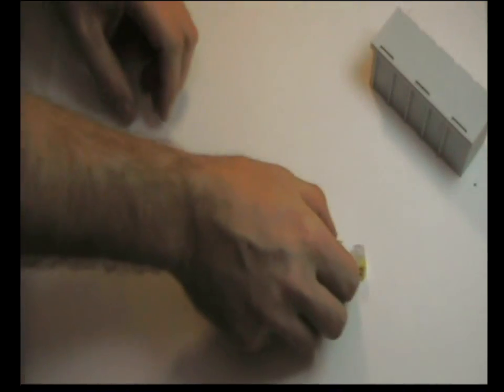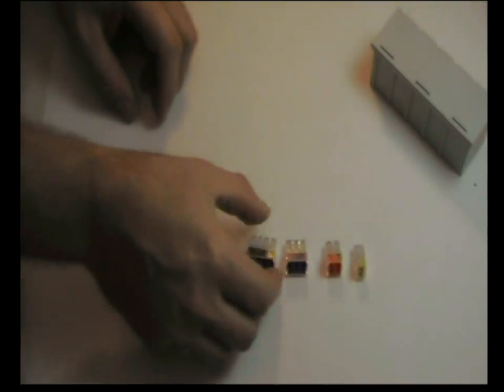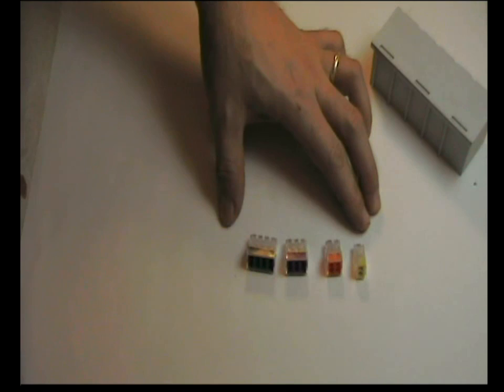The Wago box is designed to work with two types of terminals. There's push-fit, and these come in a range of sizes. Here we have a 2, 4, and 6-way, and an 8-way. These are actually 24-amp rated, and they're designed to work with cable sizes from 1 to 2.5mm.